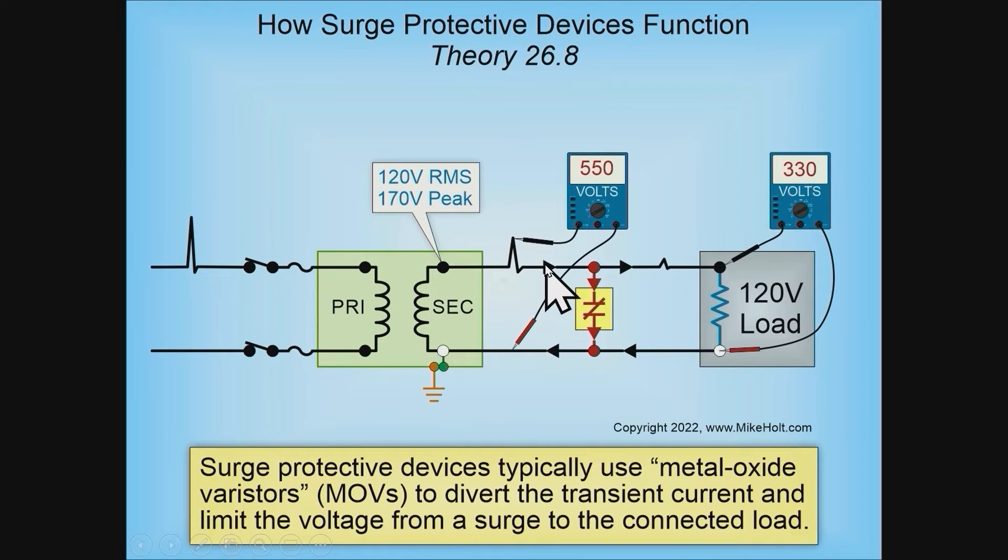Not only do you have heat at the MOVs, but because you may be carrying hundreds of amperes through the wires to achieve a 220-volt drop, the wires are heating up too. We're absorbing the transient energy by spreading it — heating the wire resistance and heating the MOVs — which all works to slow down and reduce the incoming surge.